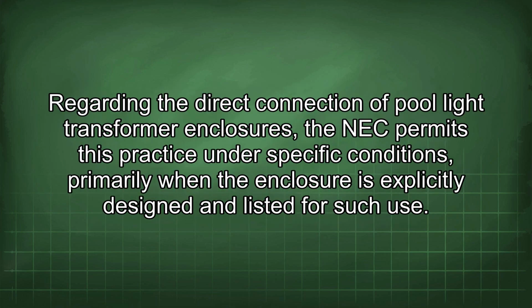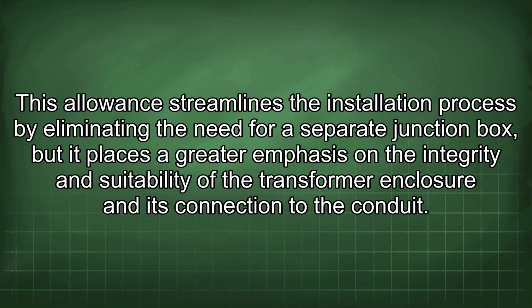Regarding the direct connection of pool light transformer enclosures, the NEC permits this practice under specific conditions, primarily when the enclosure is explicitly designed and listed for such use. This allowance streamlines the installation process by eliminating the need for a separate junction box, but it places a greater emphasis on the integrity and suitability of the transformer enclosure and its connection to the conduit.